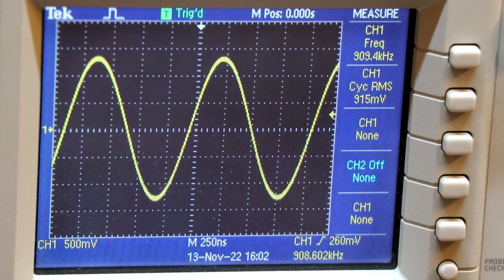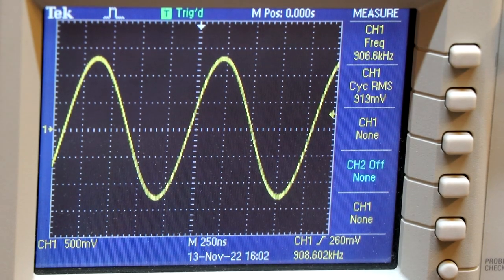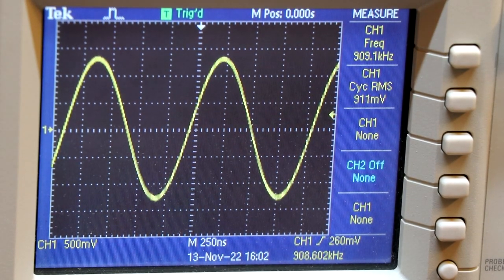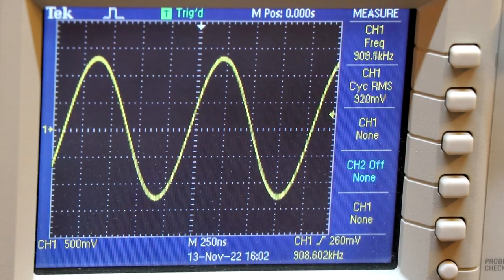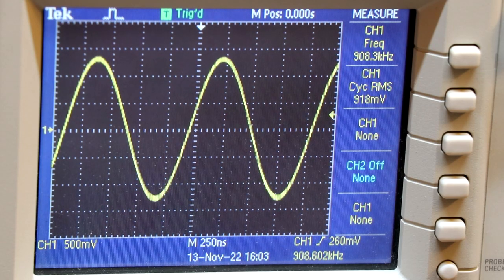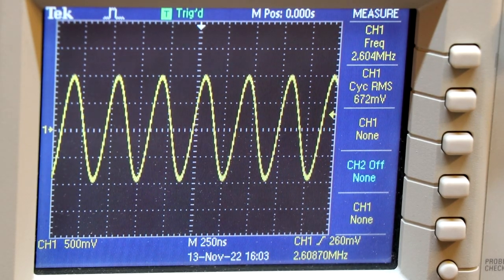So we're now on the range that covers between 900 kHz and 2.7 MHz. And we can see again at the lower end of the range we're at 900 kHz at the moment. We can see that we're just slightly high at around 910 kHz. Let's increase the frequency to the top end of the range. This should be about 2.5 MHz, actually reading 2.6.